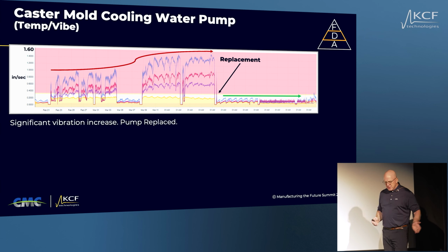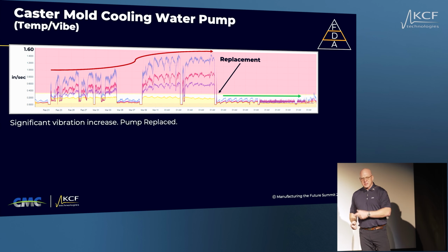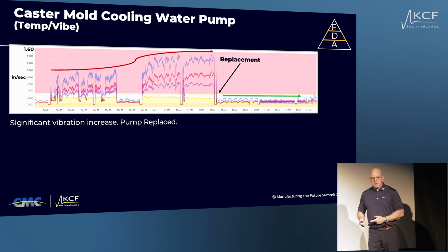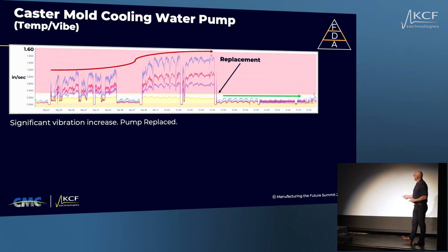So we sent the motor we'd just taken out for overhaul with the intent of replacing the second one when it came back. However, a week later, I got a call, I think it was a Friday afternoon, that this particular mold cooling water pump was running at 200 degrees after we'd changed the motor.